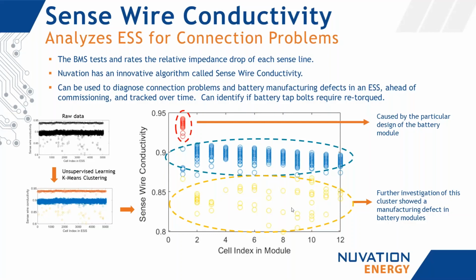So we reached out to the battery manufacturer to ask what that was about, and they said, oh, thank you for finding that—turns out there was a manufacturing change during the time your modules were being manufactured, and some bolts were not correctly torqued at the module level. So this was actually a manufacturing defect. The battery manufacturer was great about it: they came in, replaced the modules, and absorbed the whole cost.